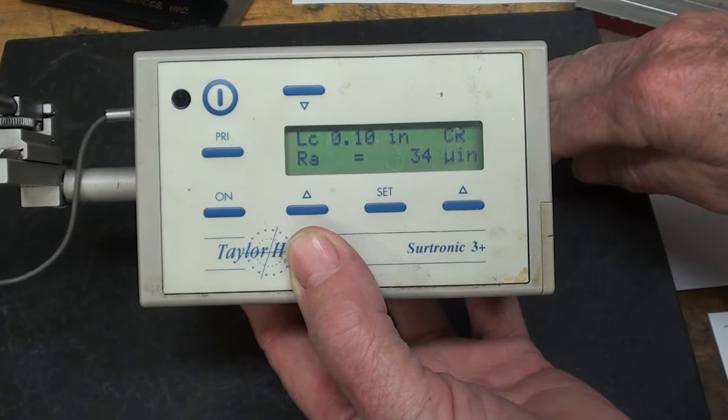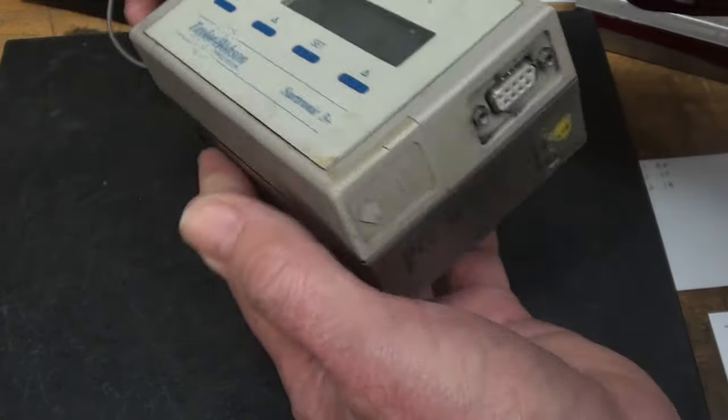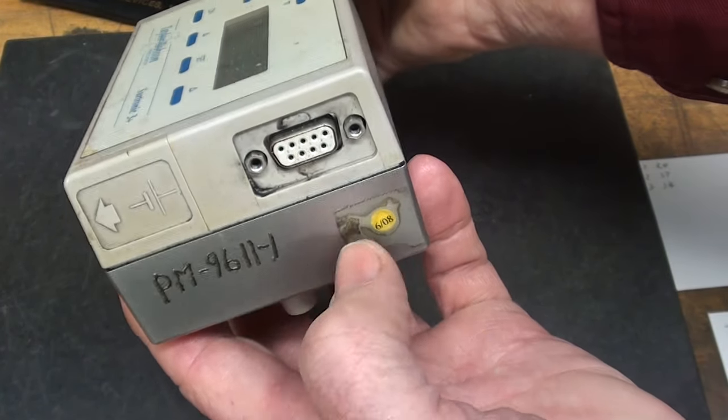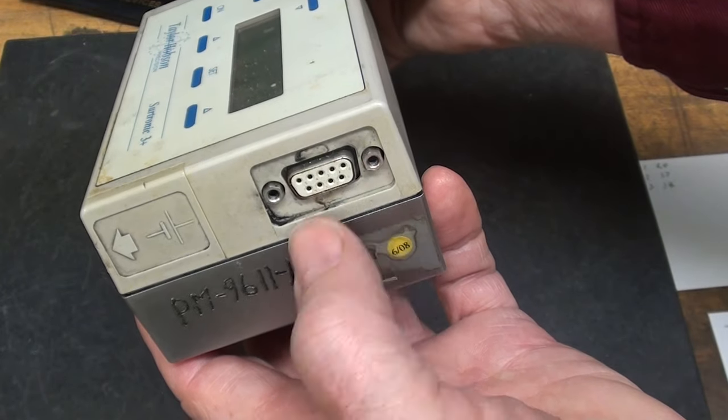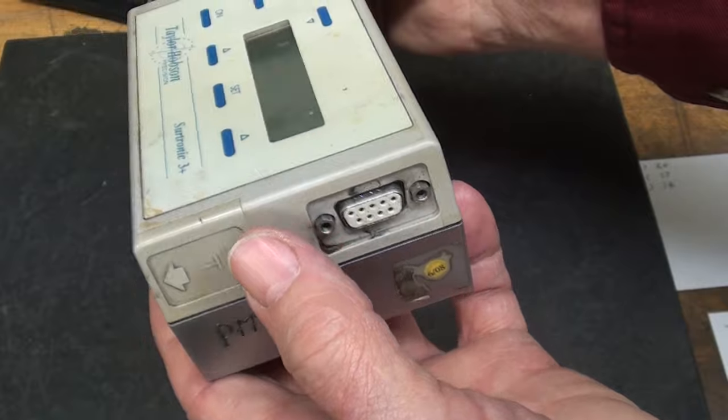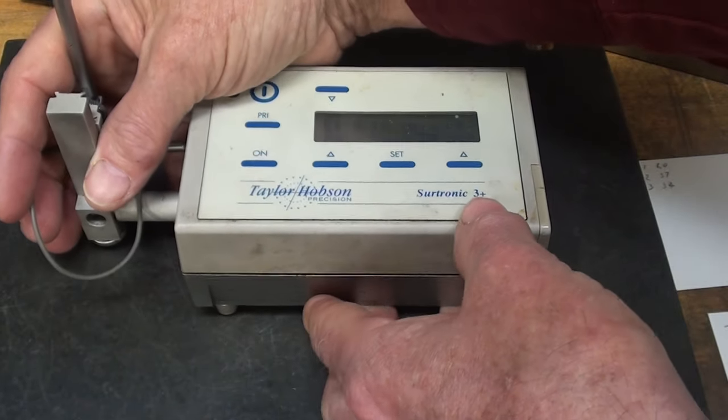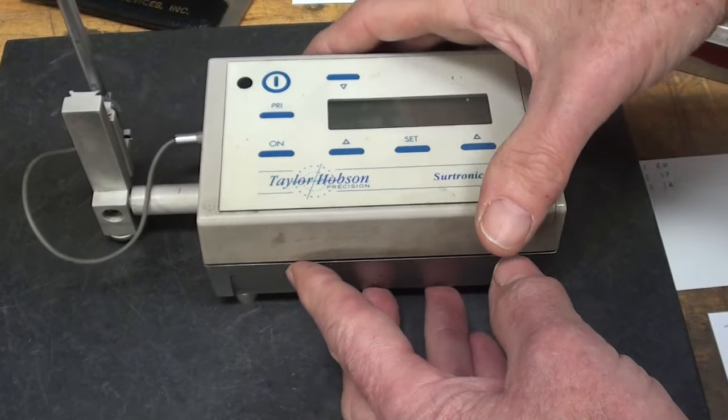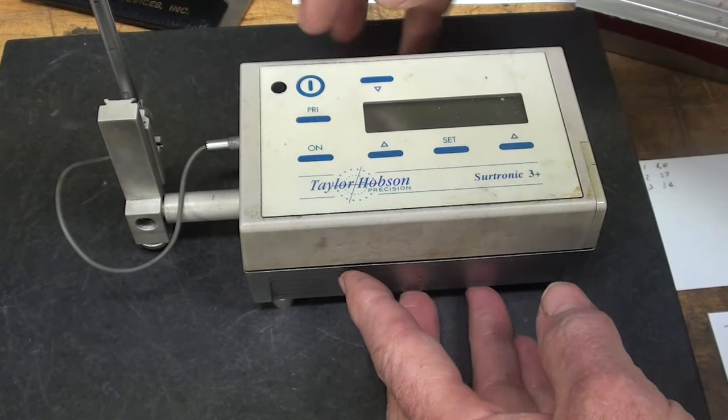It'll go off by itself. On this end again you saw that there's a port here and that could be plugged right into a printer or perhaps a computer. Graphs and prints can be made of the work and the samples that you are testing. Now how does this work? Notice when I turn it on here and get it traveling.